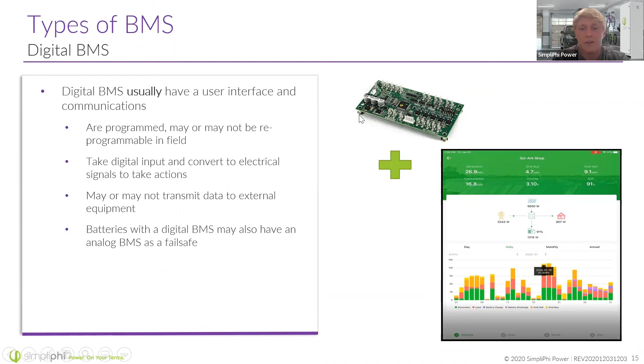In case I missed this, I'm going to go back through low versus high voltage. A SimpliPhi battery cannot be put in series, as far as our Phi and SimpliPhi products go. They're really only designed for parallel connections. The reason for this is the device inside the BMS, like a FET or a contactor, in this case with the Phi and SimpliPhi batteries, is not designed to handle more voltage than the battery. So if you've got 50 volts inside a battery and it opens the circuit, the BMS sees 50 volts, and that is totally fine.